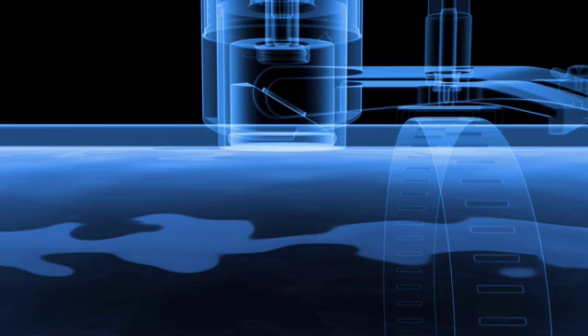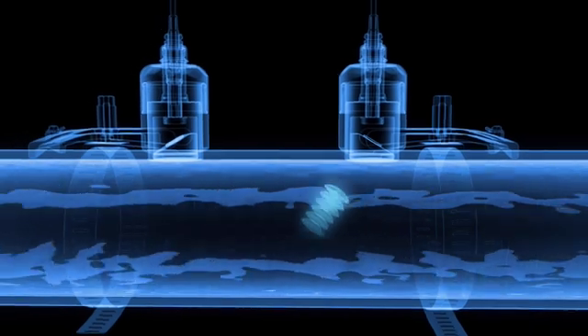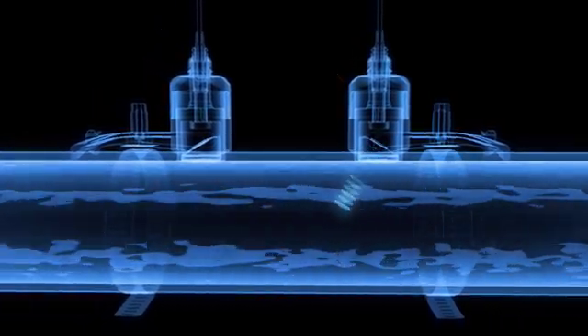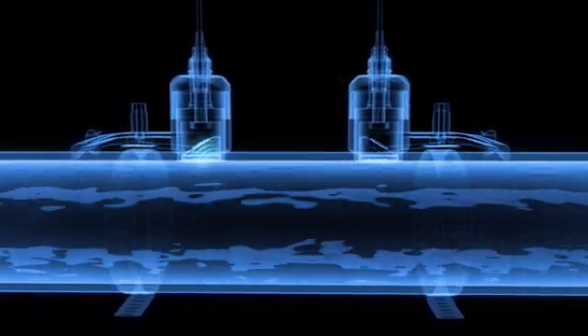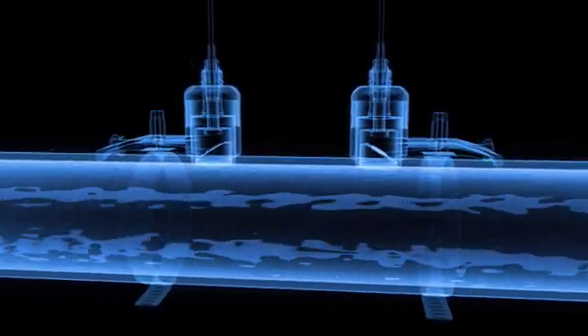With clamp-on sensors, the ultrasonic signal is passed directly through the pipe wall and into the fluid. The signal continues through the fluid, is reflected on the opposite pipe wall, and then measured by the second sensor. In this example, with a two-traverse installation.